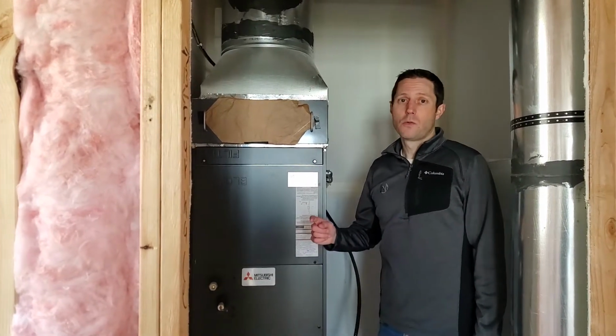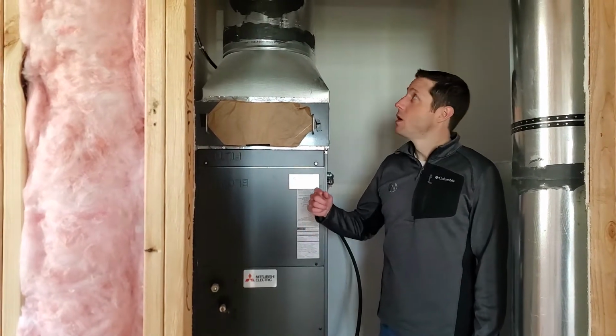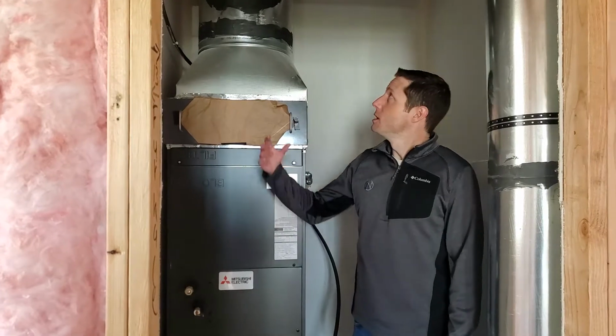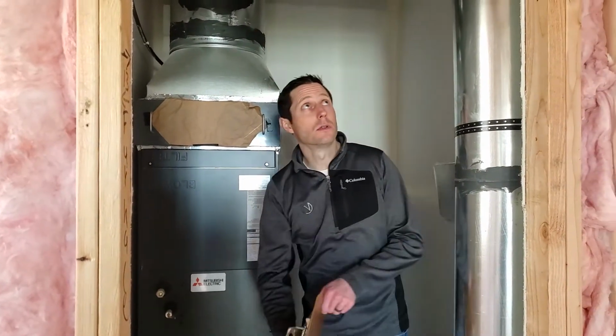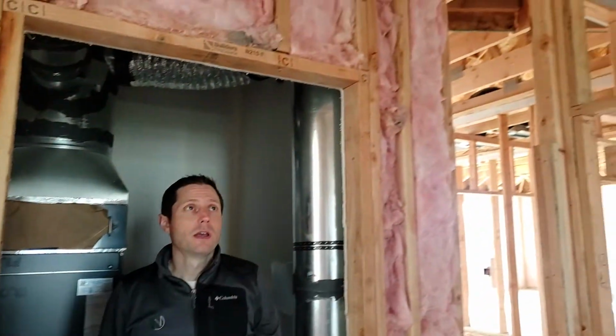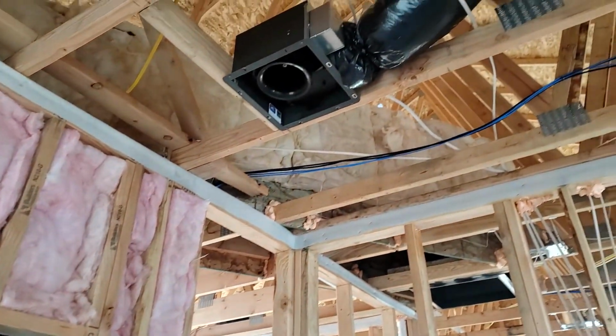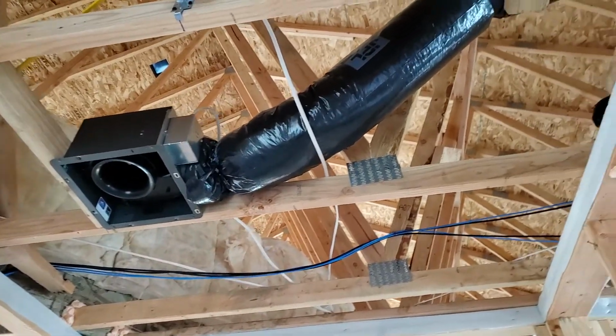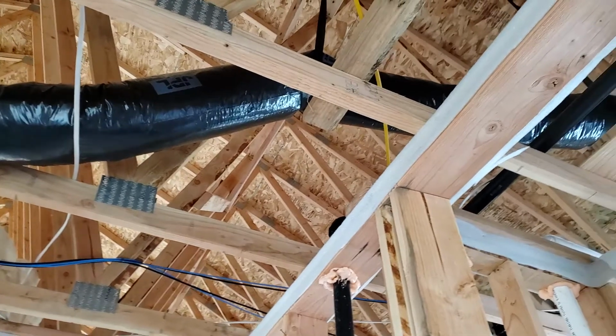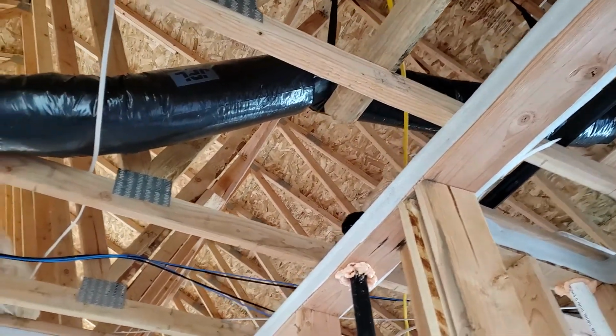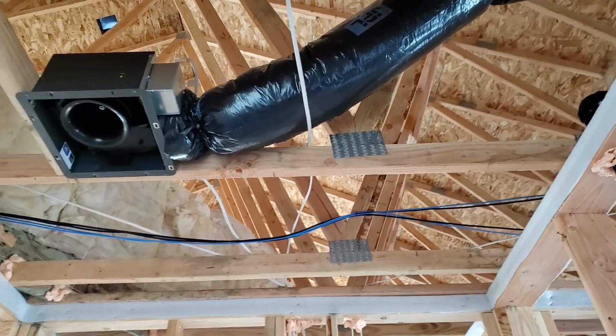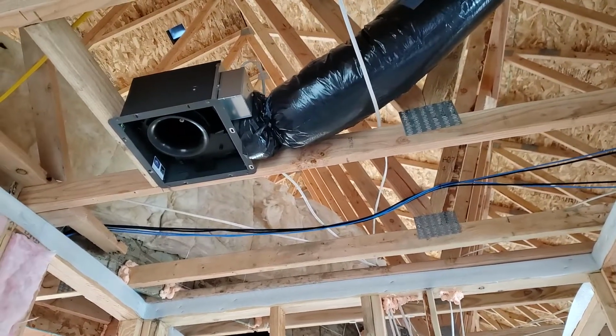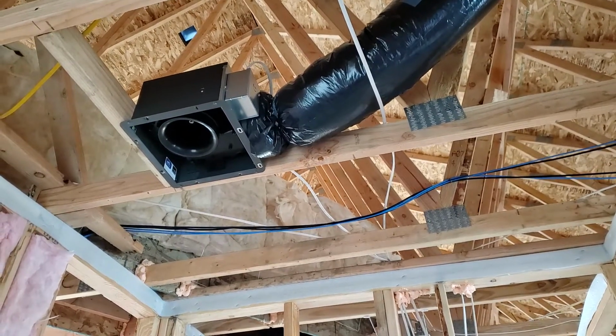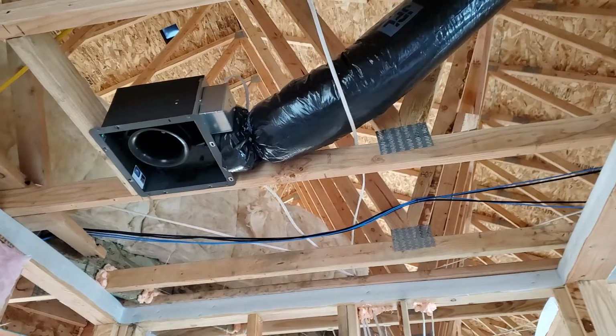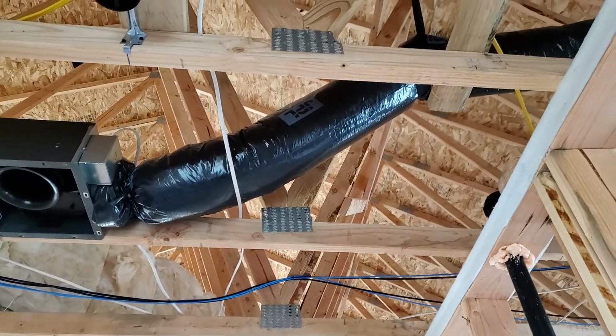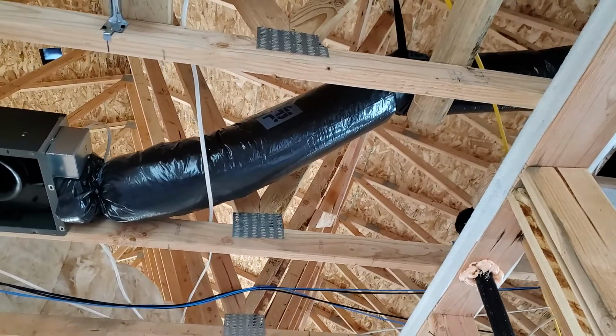Now, the code requires balanced ventilation now. So what we're doing, and we've been doing this for years, is we connect this fresh air to a laundry fan out here. And now those are interlocked, so anytime the fresh air turns on, this exhaust fan turns on. So we're sending fresh air into the house, and we're exhausting stale air from the house at the same time to avoid any pressurization or depressurization, and they're on a roughly balanced level. This particular fan has 3 settings. You can set it to a lower speed or a lower CFM, middle CFM, or higher CFM, depending on how much airflow you need. So it provides some flexibility.